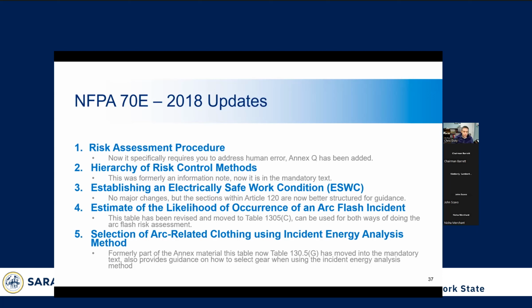Typically, that's shutting down the system, right? If you have to get into it, you don't want it to be energized. That just opens you up to the potential to get electrocuted, which obviously everyone wants to avoid. It also has information on how to estimate the likelihood of an arc flash incident occurring. Arc flash is super, super important to be aware of because it can cause a ton of damage to the inspector and property, and it can potentially kill you. So you want to make sure you're aware of the likelihood of that happening.